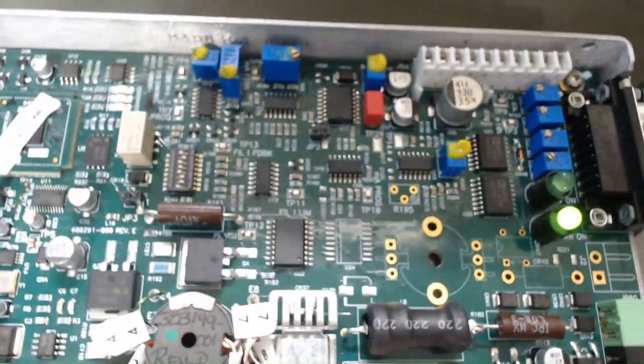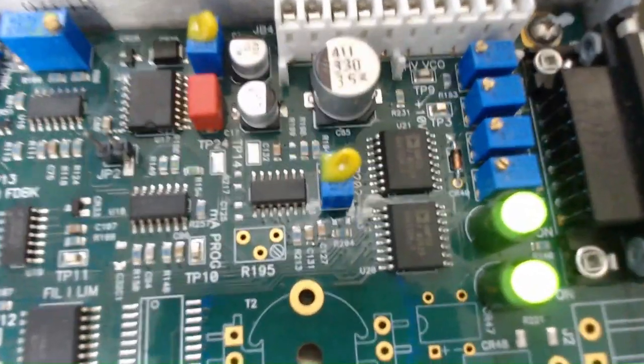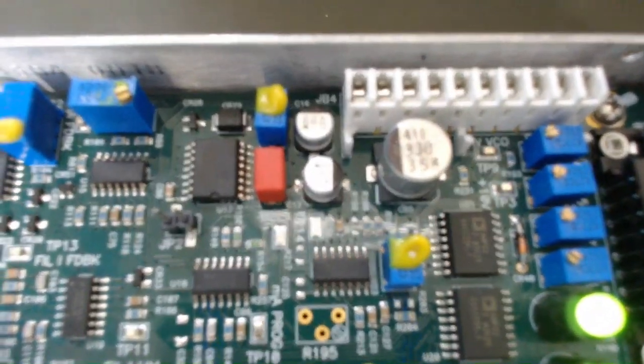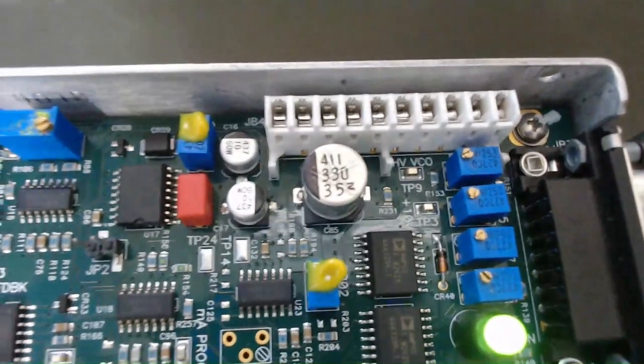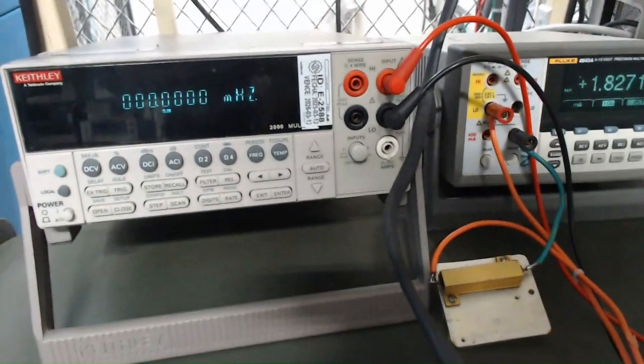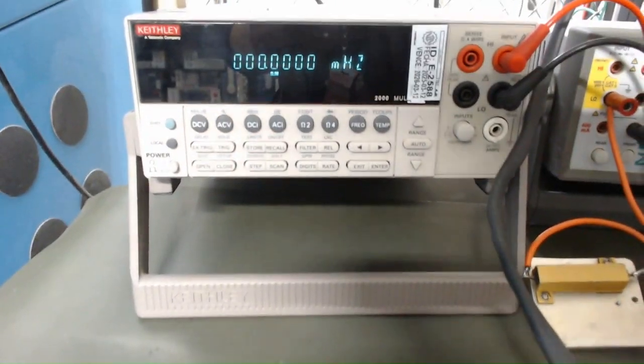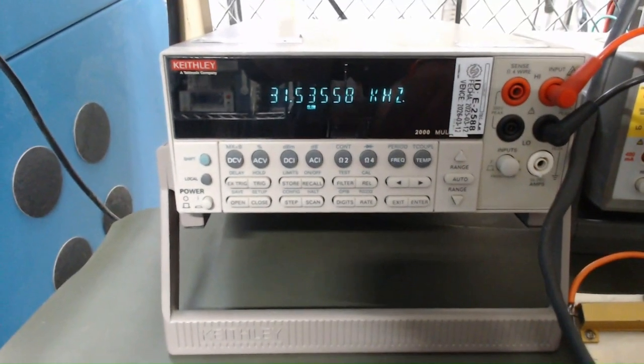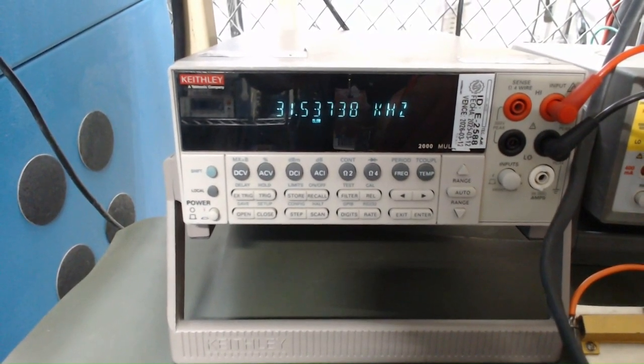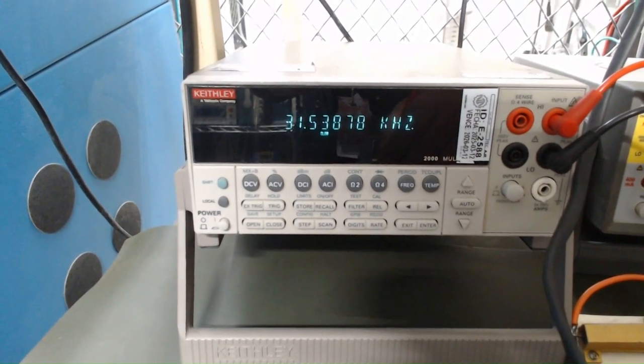The next test to be carried is the operating frequency tests, where the inverter frequency is verified to confirm it is working within specification. This will be measured at TP9 with the unit providing full rated output. Frequency should be in the range of 30 kHz to 34.9 kHz. Measurements indicate that the frequency is at 31.53 kHz, which is within the specification. Value is recorded in the datasheet.